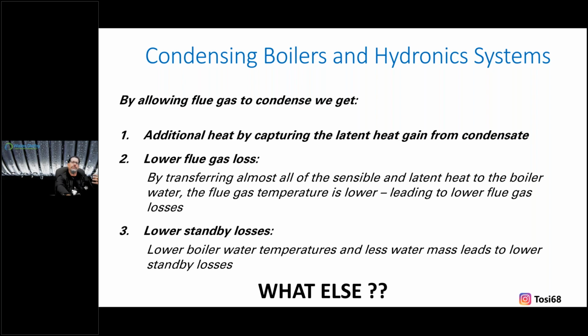Think about if we have this higher flue temperature that has that product of combustion, right? Let's call it an acid almost. It's trying to leave the envelope of the building, and with our venting now, it recirculates right back into our fresh air. That now gets brought back into the product of combustion. And this is where we're killing really expensive equipment and the components and seeing some reoccurring nightmare jobs because we just don't see where the problem is. And we think it could be component failure when you need to start understanding the proper installation.